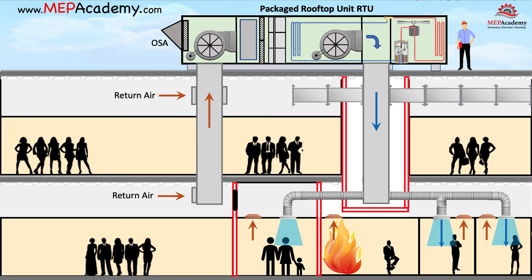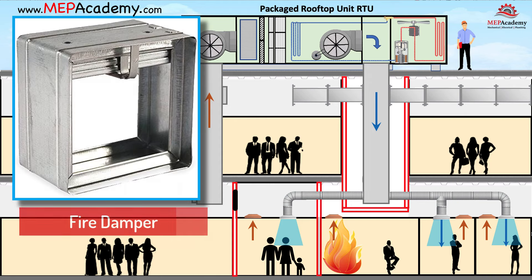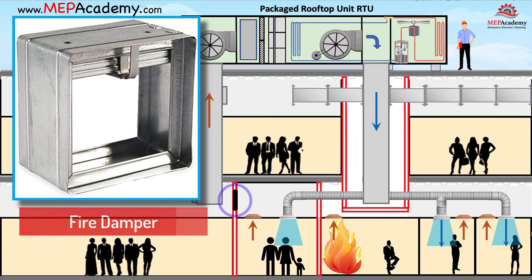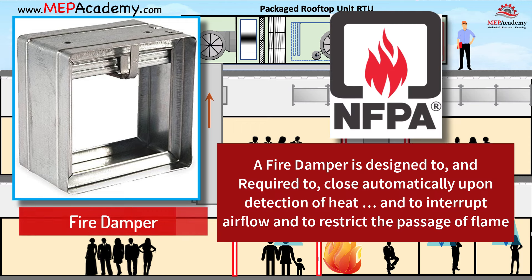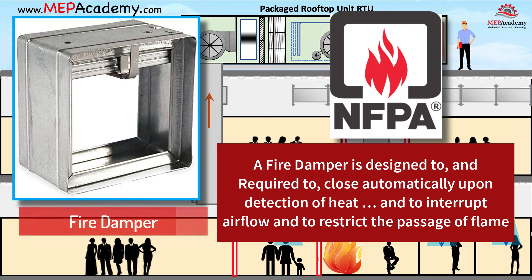Since we have penetrated the fire-rated wall, we'll need to maintain the fire rating by installing a rated fire damper at the supply and return air wall penetration. Here is the definition of a fire damper according to the NFPA, National Fire Protection Association: a fire damper is designed to and required to close automatically upon detection of heat, such as a fusible link or heat detector, and to interrupt airflow and to restrict the passage of flame.